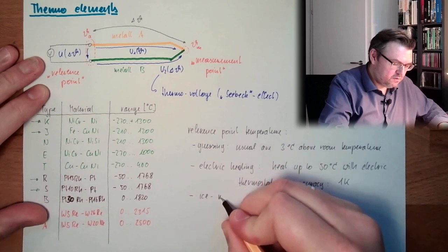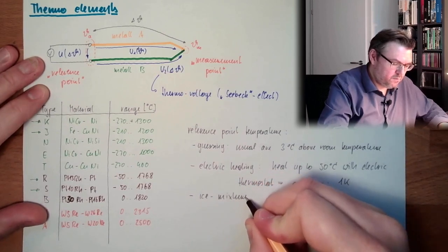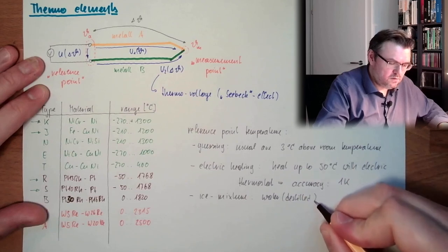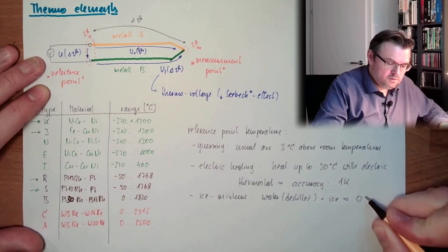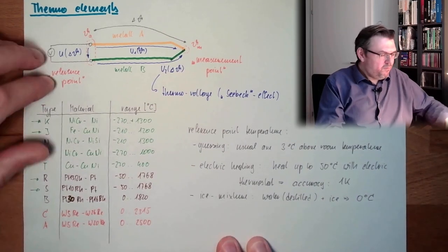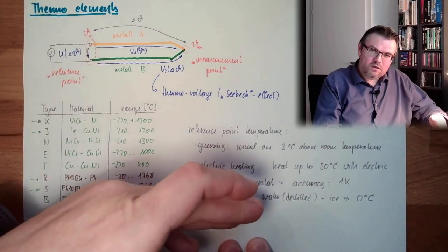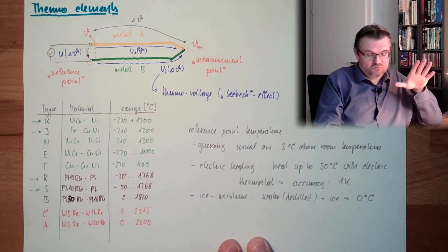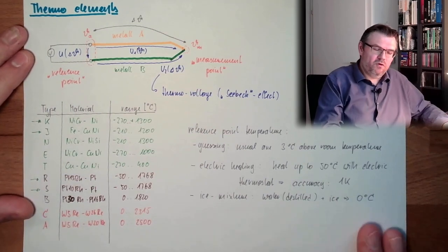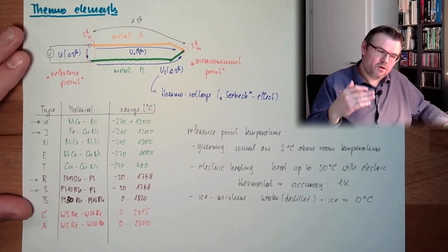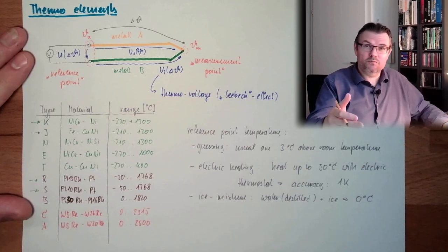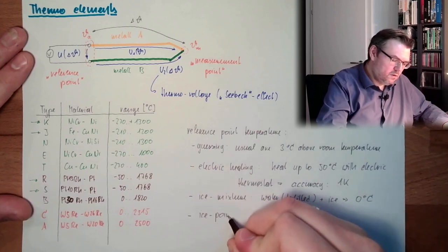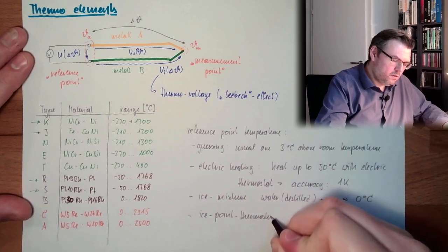Water distilled and ice, zero degrees Celsius. We simply place this into an ice mixture, distilled water to be electrically isolating, and ice, zero degrees Celsius. Quite accurate. However, this is for experimental things, high quality experimental measurements. For permanent measurements, you do not want to have a bucket full of ice. So you are using an ice point simulator.